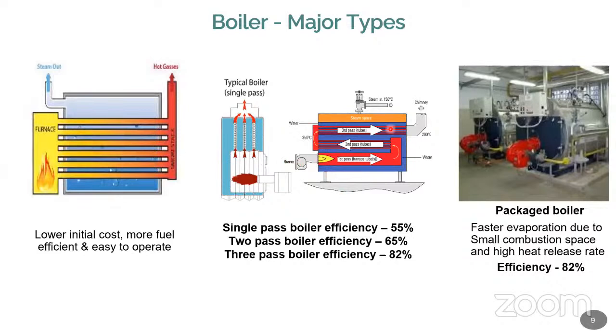First pass, second pass, third pass, it is going to be alternate. It is not in the same direction. It is alternate, and finally it will produce the steam. The steam will go out, and through the chimney the flue gas will go out. Sometimes the packaged boiler is completely closed. Everything is completely closed. This is called a packaged boiler. It is a very fast operation, and the efficiency is going to be around 82%. But normally, for a single pass boiler the efficiency is going to be 55, and for a 3-pass boiler it is going to be 82.